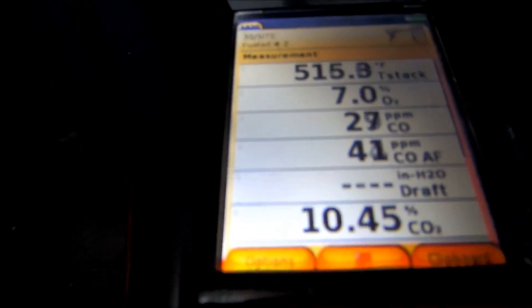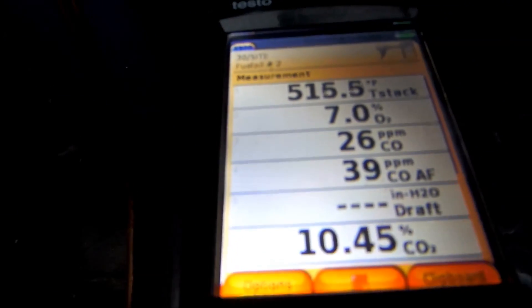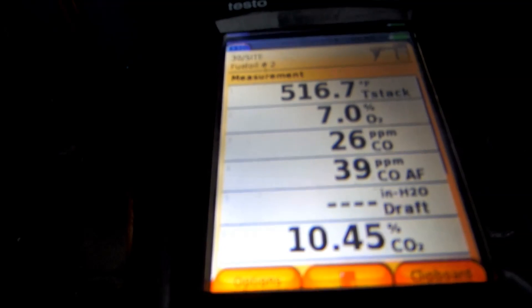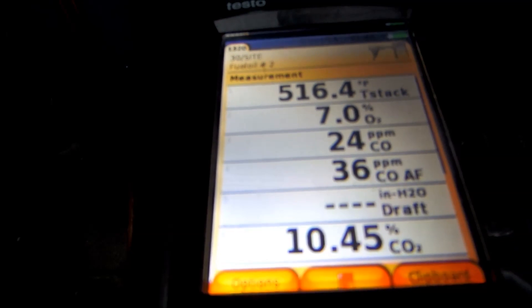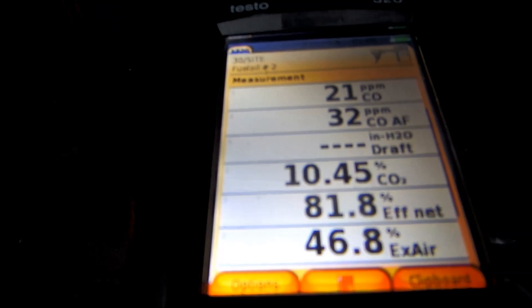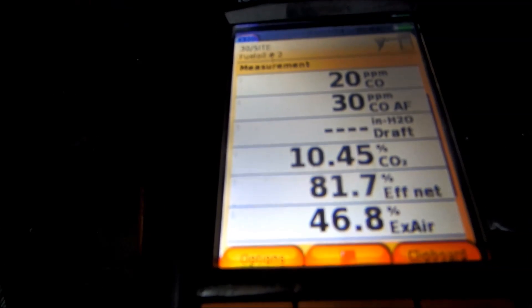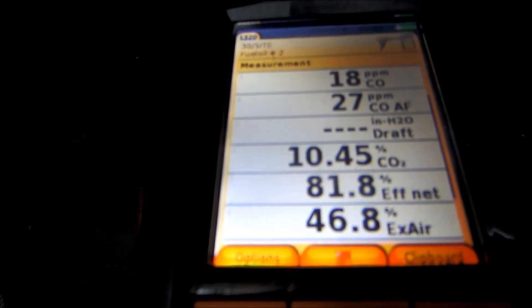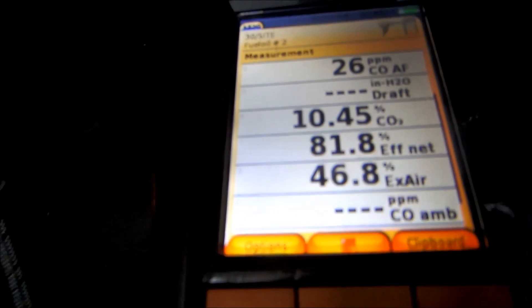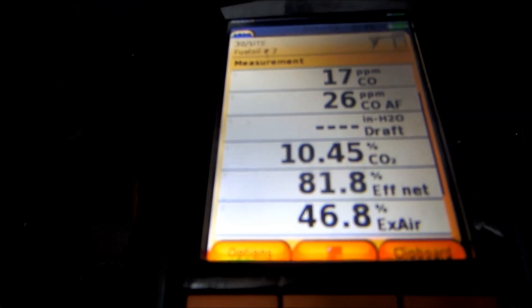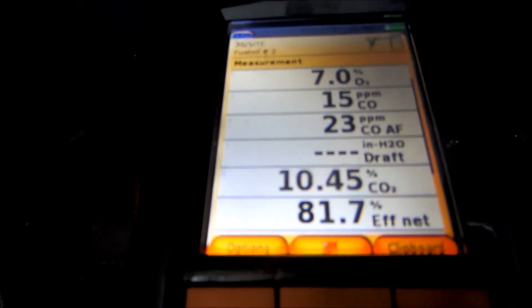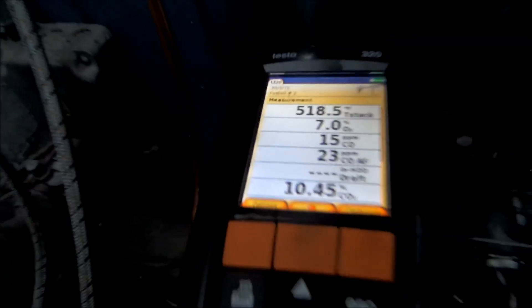All right, the CO's dropping, but I'm fine with that 10.45, 7% oxygen, 81%. You can't always get the excess air where you want it. You know, I had a guy say, oh, it's going to be 20 to 25%. You can't, not always.